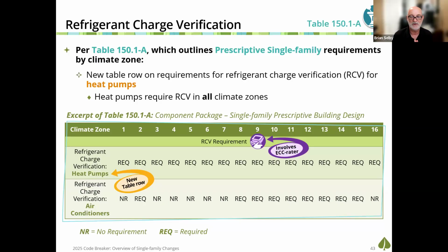All right, moving to some of our mechanical system prescriptive requirements. You'll see that refrigerant charge verification is prescriptively required in all 16 climate zones if a heat pump is used to meet those requirements. This is a good thing. This is a quality assurance to ensure that the technician installing that unit installed the proper amount of refrigerant, not too much, not too little. So very important for heat pumps that they are charged correctly. Now, you'll see that for other types of air conditioners, when a heat pump is not used, it's still prescriptively required in certain climate zones.